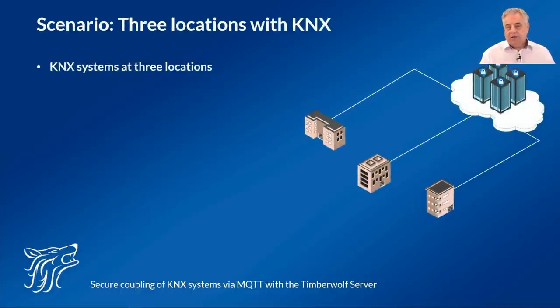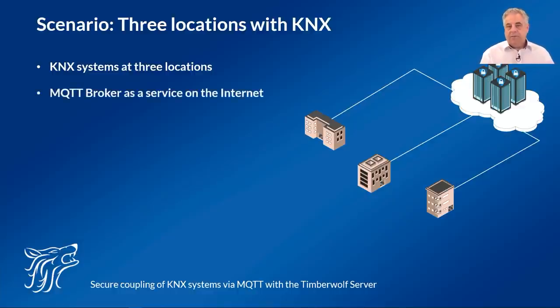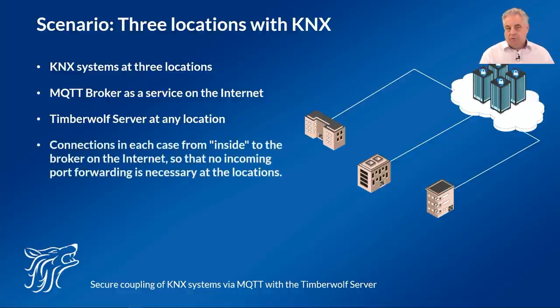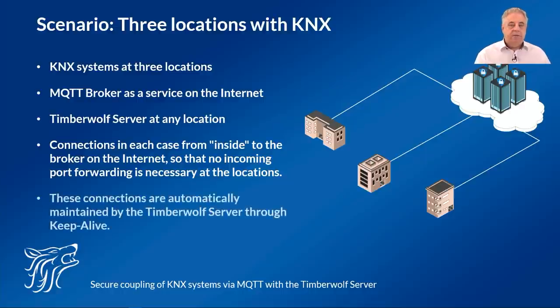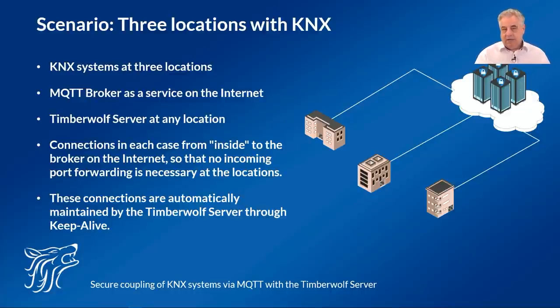Let's look at the scenario we are about to realize. KNX systems at three locations are to be linked together. The coupling takes place via an MQTT broker on the internet. Each site is equipped with a Timberwolf server. No port forwarding is required for this — the Timberwolf servers communicate from the inside with the MQTT broker and keep the connection open with KeepAlive packets so that subscriptions to topics can be received at any time.